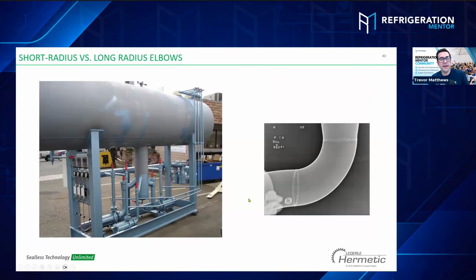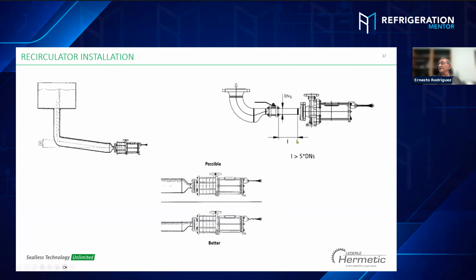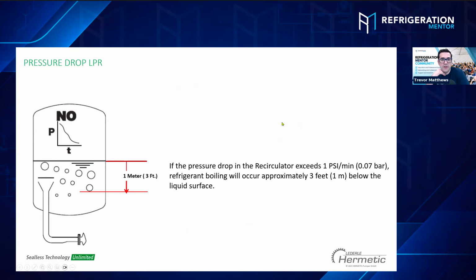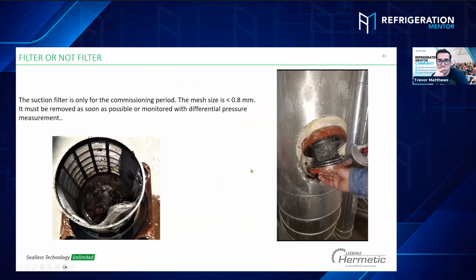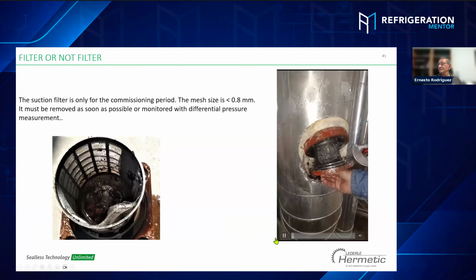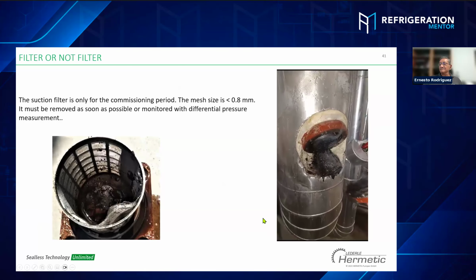Is there any rule of thumb, like 3 to 1 the size of the pipe, 5 to 1, or just a foot or 2 feet away? Basically, we can use the same rule, five times the diameter, to keep the turbulence down. Okay, great. It's the same rule. There you go.